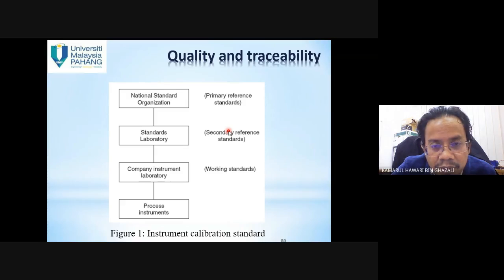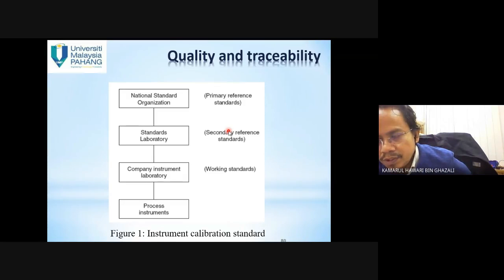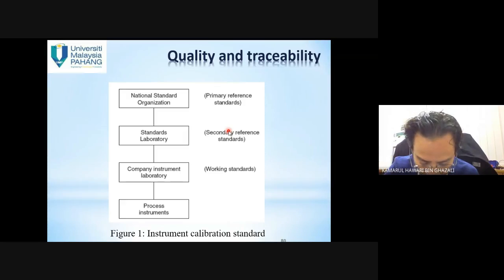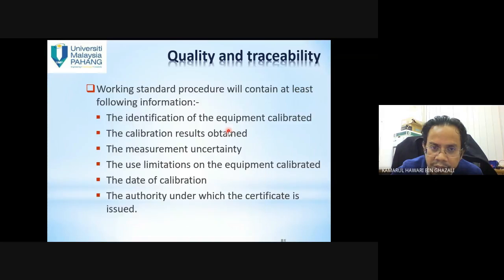If there is enforcement to check your weighing instrument, whether you have calibrated it or not, then you can show the certificate. Okay, if you don't have that certificate, then you will be fined lah, kan, summoned by the local authority. Because weighing is very sensitive. Some of the hawker kedai-kedai tu, sometimes they adjust it by themselves, kan. So it needs calibration in order to get a precise or accurate reading.